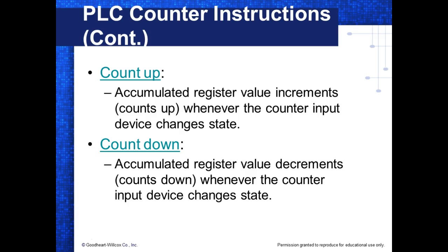If you look at the data book that goes to the instruction set for the 1100 PLC or any Allen-Bradley PLC, you will never see the word accumulator register. A register is inside the microprocessor. These are not inside the microprocessor. They're out in the RAM memory of the PLC. So technically, these are not registers. Technically, these are words. So the accumulator occupies a complete word.